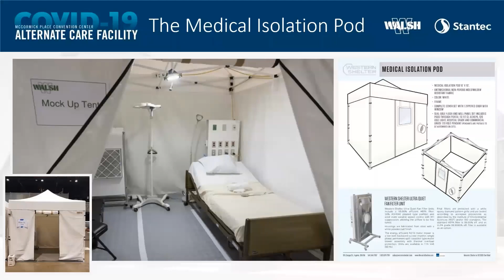Next slide. The patient rooms themselves, or spaces, should we say, for the acute care COVID patients were individual medical isolation pods. The air would move through them and be drawn to the HEPA filter, which is pictured on the left-hand side of the picture on the left. This air would then be drawn through a HEPA filter machine and pulled up through the air systems that were ducted and out of the building. This facility created a negative air pressure HEPA filter environment. We also had modular head walls, and this particular cubicle is a critical care unit because it has medical air in addition to medical vacuum and oxygen. We had 4 emergency outlets and 4 normal outlets for each of the critical care pods in Hall C. Next slide.